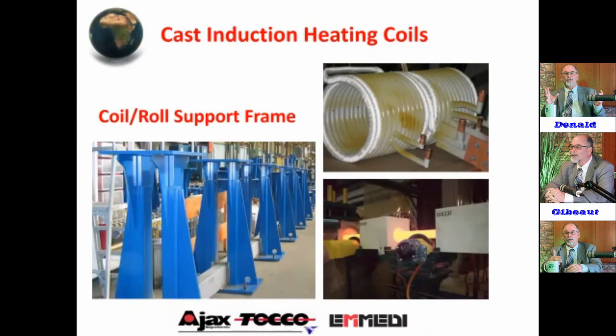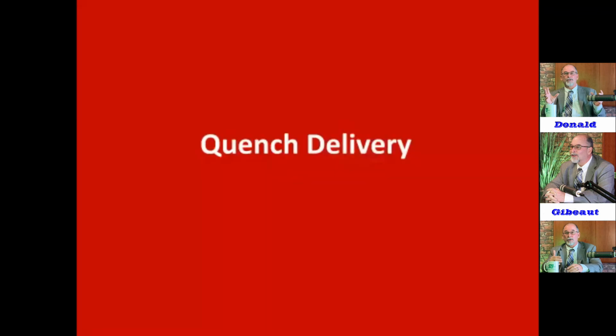And people say, oh, man, that's a lot more cost. No, it's not. You're making a mold, you're pouring the coils on the inside anyway. It's just a little bit more raw materials, but a lot less than buying all these high temperature boards that now do not hold up. To the left, you can see that 1 degree slope. These are coil stands that a block goes on top of to keep that quench water from creeping back up. So now we're going to look at the quench system.